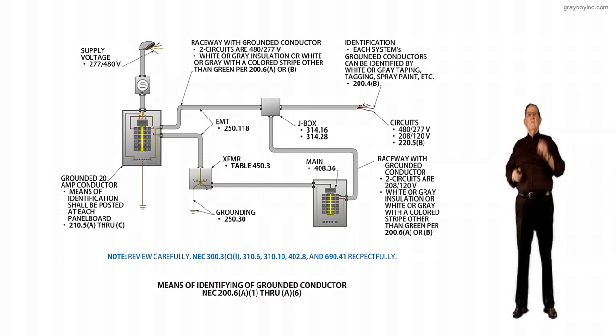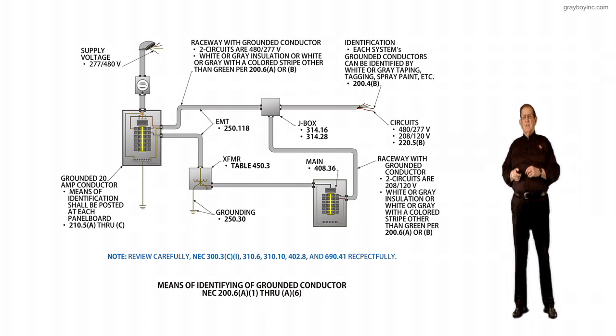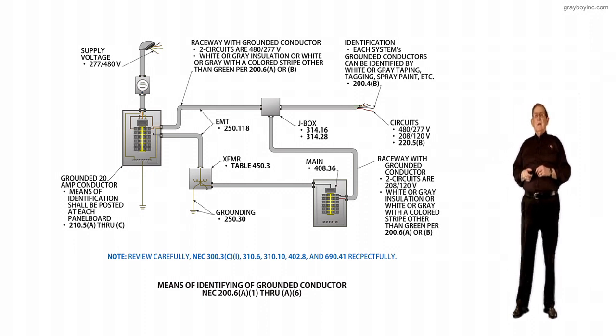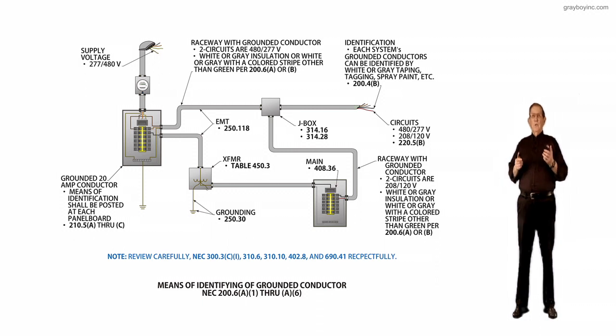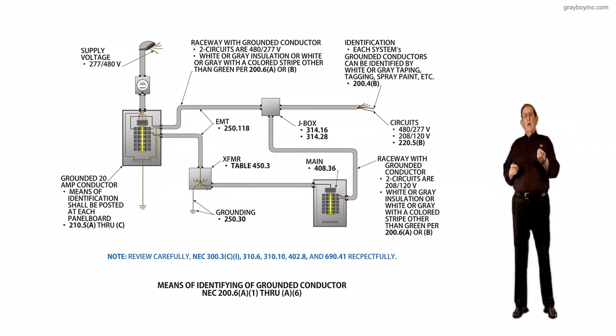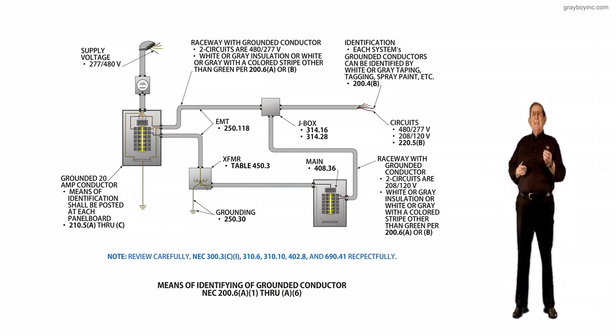Now in the illustration itself, you can see that we have 480, 277 at the weatherhead coming down to the panel. Then we have a breaker feeding a transformer, and we size the overcurrent device from table 450.3 on the primary side. On the secondary side, we make a tap, and that tap is 240.21C, 1, 2, or 3, 6. And then notice if it's say an industrial location, then we go to 240.92C for a 100-foot tap. And any length you want, basically, I believe it's 240.92E is an ED, and that kind of outlines how we would have to identify that grounded conductor.